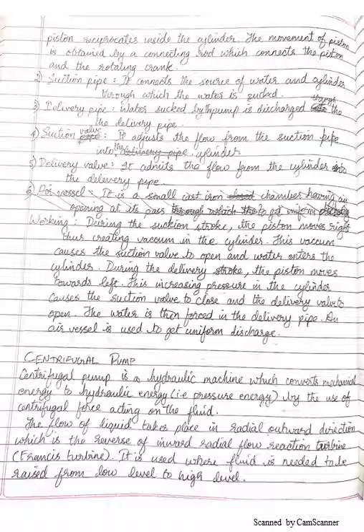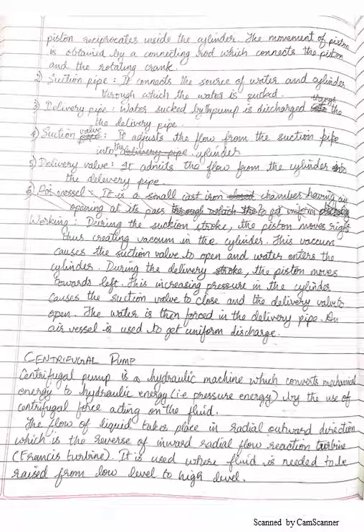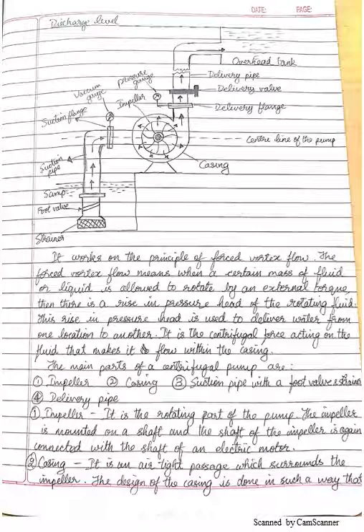A centrifugal pump is a hydraulic machine which converts mechanical energy into hydraulic energy - that is pressure energy - by the use of centrifugal force. Just as a merry-go-round creates centrifugal force as it rotates, the centrifugal force in this pump moves the liquid from one end to the other. The liquid moves in the radially outward direction, which is opposite to the Francis turbine where liquid moves in the radial inward direction.